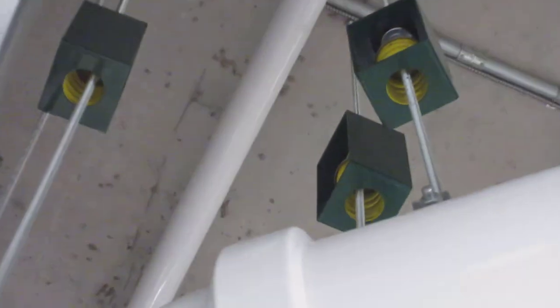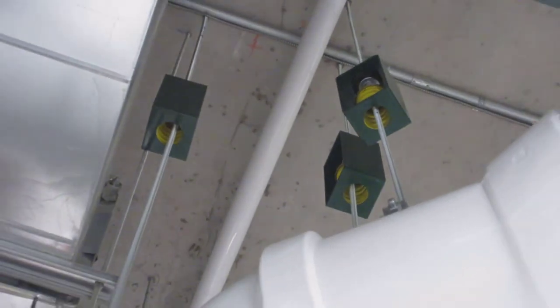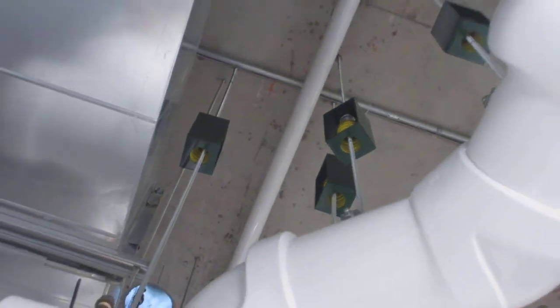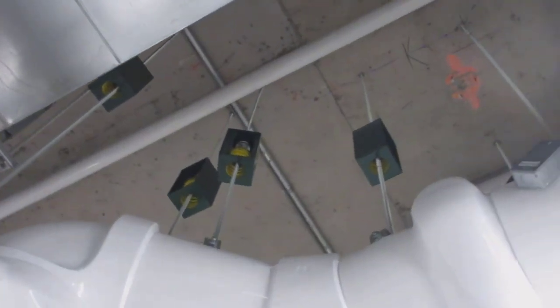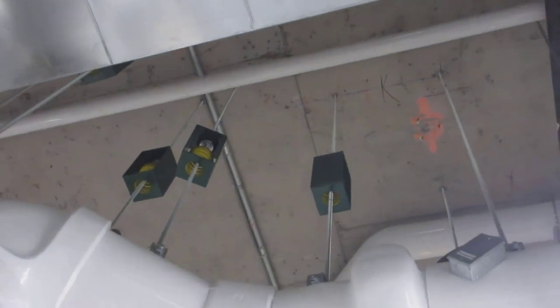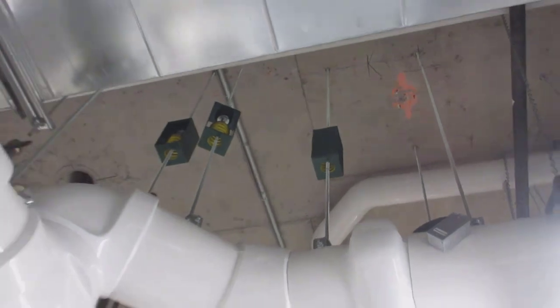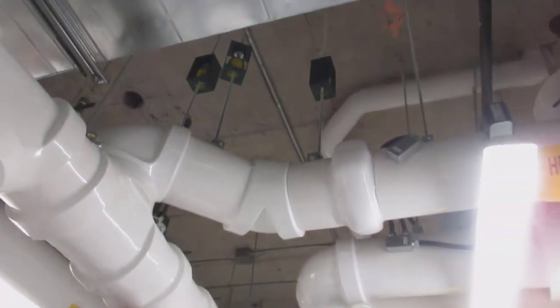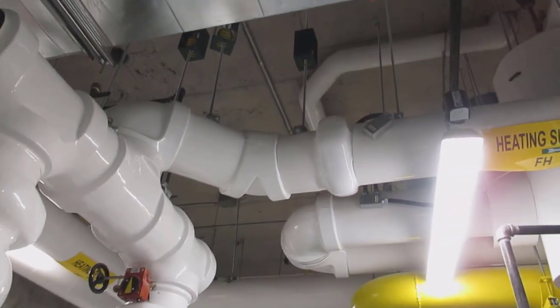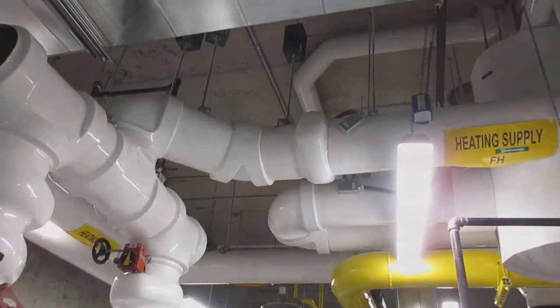These hangers all appear to be installed okay, considering the six points we discussed earlier. The upper and lower rods all appear straight, and there is no metal to metal contact that would short circuit the isolation.